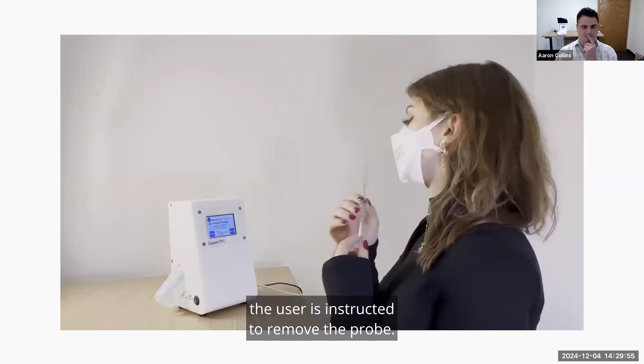Once the secondary ambient concentration measurement is complete, the fitted filtration efficiency is computed along with the N99 and N100 fit factor. These are compared to the pass level set in the device and then shown to the user on the integrated screen or via the app. One big advantage of the OpenFit solution is that at the completion of the test, the respirator has been validated in the as-worn and as-used state. Our experimental work has shown the introduction and removal of the probe has no impact to the seal of the respirator, meaning for the first time, users of respiratory protection can quantitatively ensure the product is properly donned before exposure with no modification to the device.